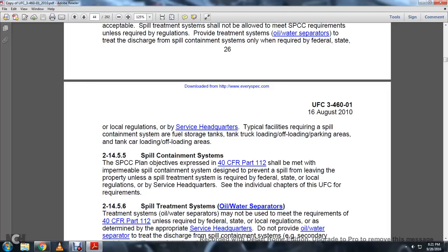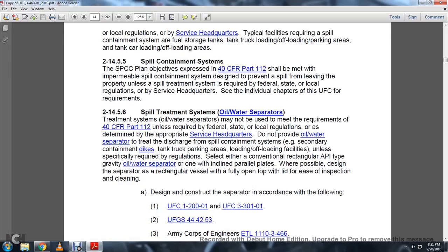214.5.5 Spill containment system. The spill prevention control countermeasure plan objectives as expressed in 40 CFR Part 112 shall meet the impermeable spill containment system designed to prevent the spill from leaving the property, unless the spill treatment system is required by the federal, state, and local regulation or service headquarters. See individual chapters of the Unified Facilities Criteria, Facility Criteria Requirements.